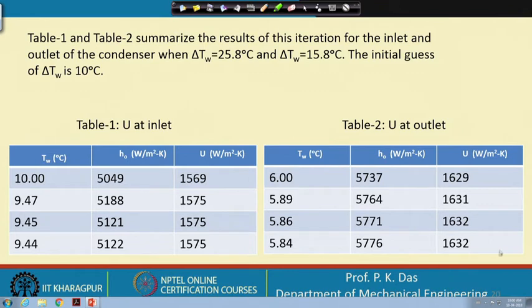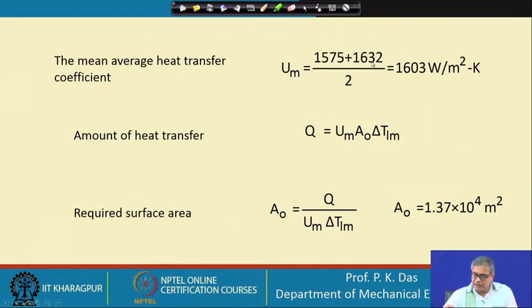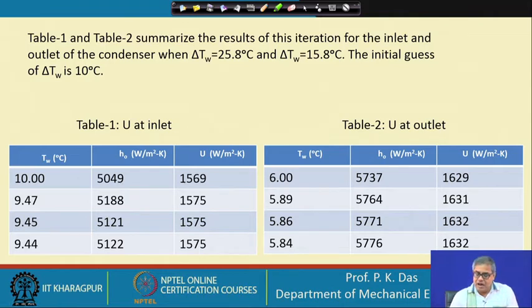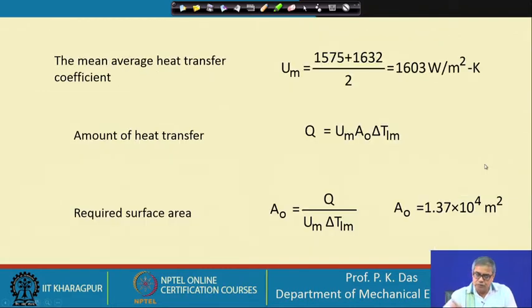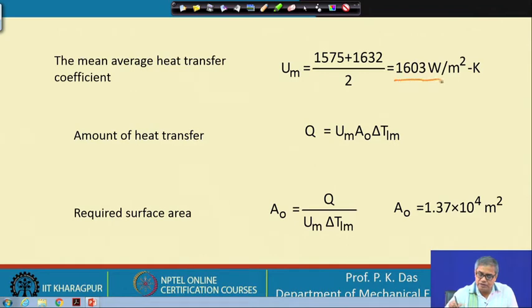From the previous calculations, the inlet-side overall heat transfer coefficient is 1575 W/m²K and the outlet-side is 1632 W/m²K. With these two values we calculate the average heat transfer coefficient. The total rate of heat transfer Q is already known from earlier — we know how much steam needs to be condensed and in what condition it enters the condenser.